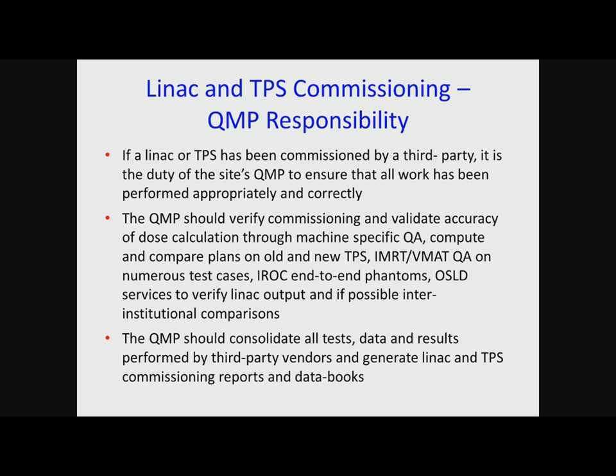But I would spot check it. If I was going to a new clinic in the middle of nowhere and I became the physicist, I would want to make sure that the machine I'm inheriting from the previous physicist is up to par. And so you do spot checks. You check the TG-51, which doesn't take a couple of hours. You can do OSLD measurements. You can get OSLDs from the RDS or IROC and do an output check of the machine. It's an independent check, and that's very important.